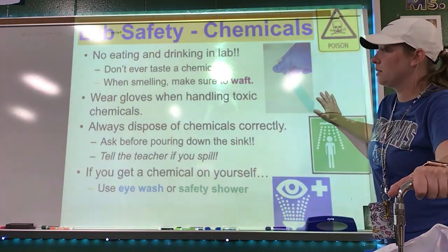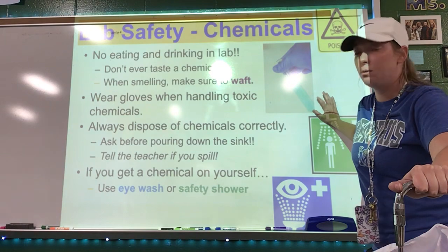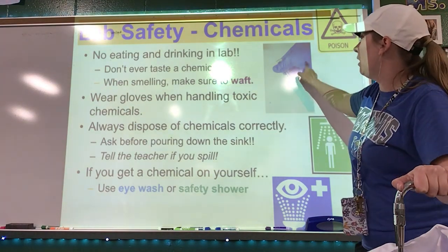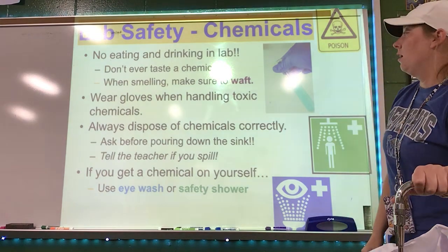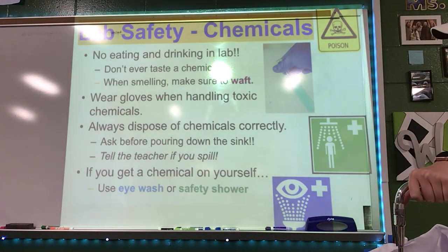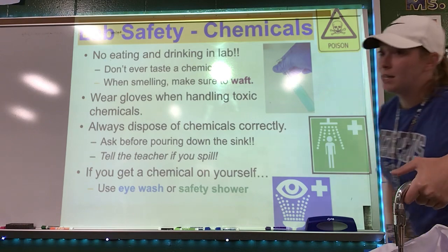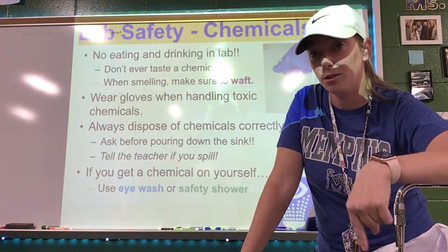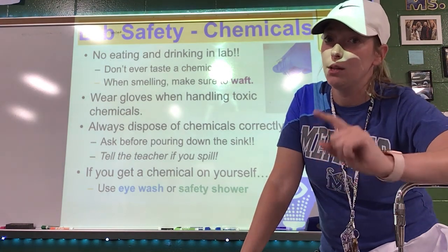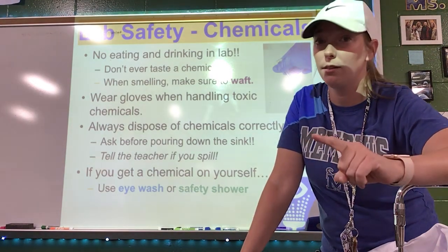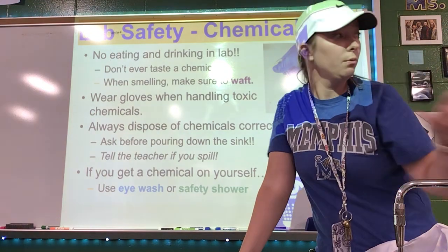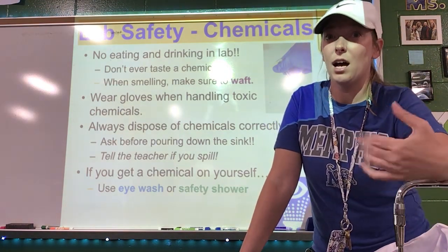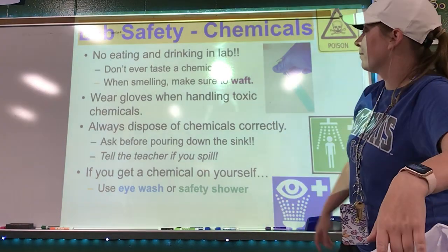Wearing gloves when handling toxic chemicals. In general, in regular chemistry, we don't use anything that's too toxic that we have to wear gloves for. Always dispose of chemicals correctly. Ask before pouring down the drain. That's because some chemicals are very corrosive and will eat away at metal in the drain. So if I don't tell you it can go down the sink, do not put it down the sink. Generally, we will put it in the fume hood, which is right next to where my computer goes, and we will keep it safe there, and then I will take care of it at a later date.